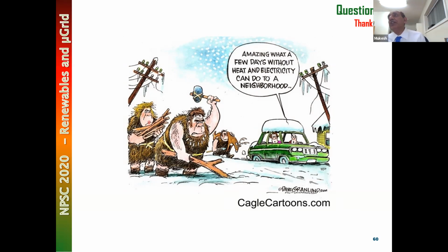I think this is a very good question, an excellent question. For the one microgrid I mentioned, it was not intended to be an unplanned microgrid. It was intended to be a planned microgrid. That means the setting groups are manually changed. In order to do automatic setting group changes, all we needed is a communication SCADA signal for a transition. And for two setting groups, all we needed was the two bus breaker status. If those two bus breakers are open, then we can switch.